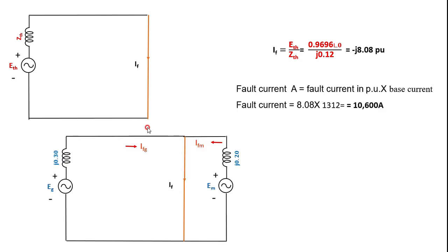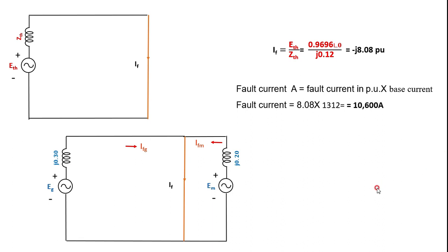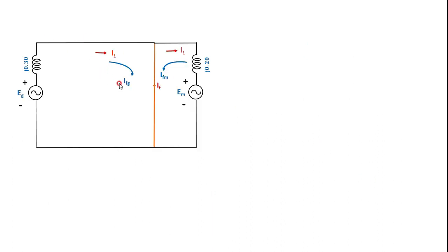Redrawing the fault condition diagram of the network: at the fault point, the total fault current is contributed from both the generator and the motor. Apart from the fault current components IFG and IFM, there is also the pre-fault load current IL. Using the parallel branch current divider method, I will calculate IFG and IFM — the fault current contributions from the generator and the motor.